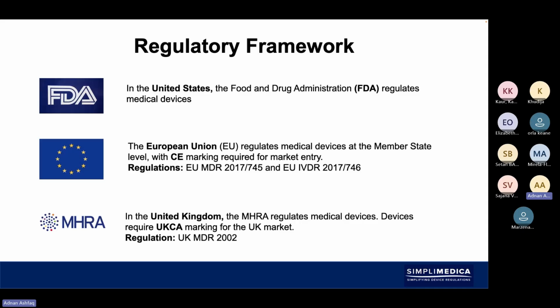So the US FDA would regulate the medical devices, whereas in Europe, it's been delegated to individual organizations, which are called notified bodies, and they are the ones that are responsible for certifying individual legal manufacturers with CE certificates. In the UK, we also have something similar to Europe, where MHRA, which is the government agency, then the competent authority, would then regulate medical devices and designate specific companies, which are notified bodies, to then provide UKCA marking. So that's one of the differences.